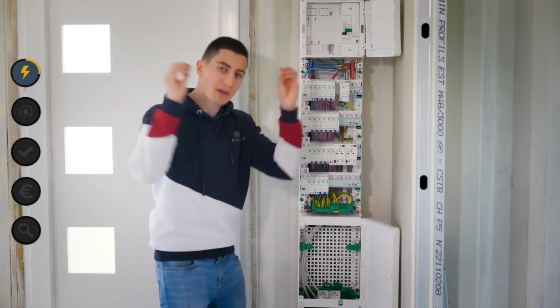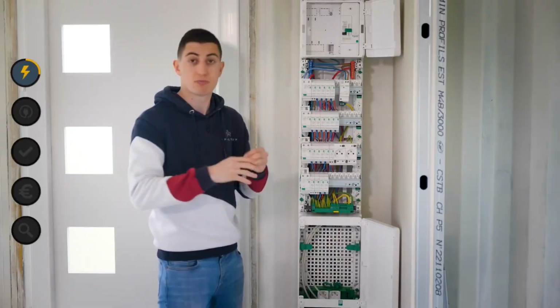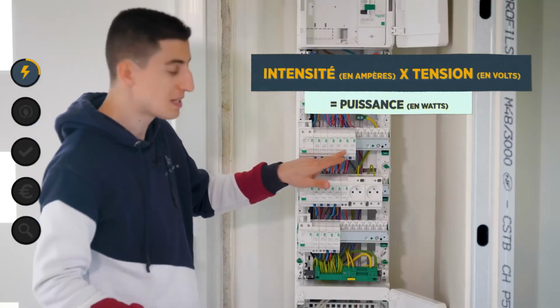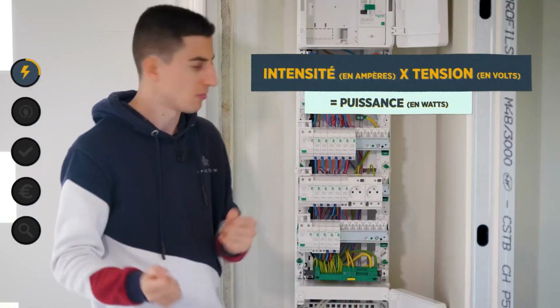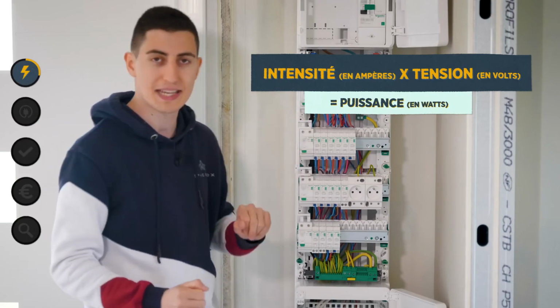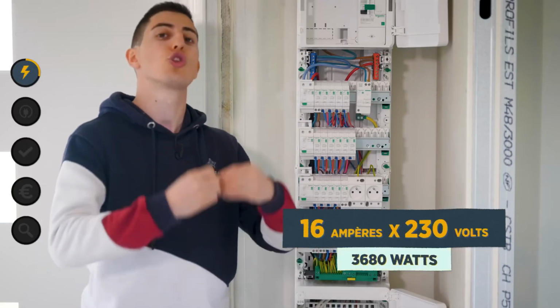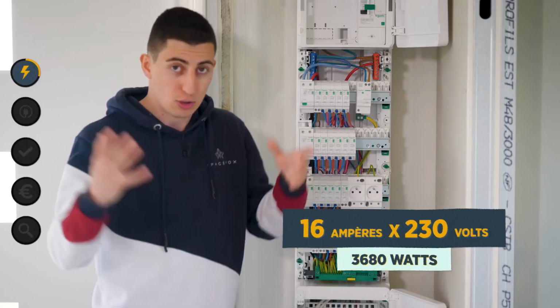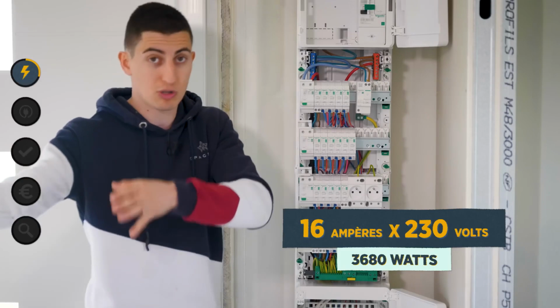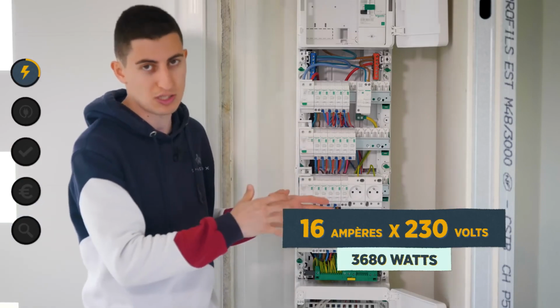If you want to calculate more precisely what power you need, it's simple: just multiply the amperes by the volts. For example, with a 16 ampere circuit breaker on 230 volts, that gives us 16 times 230, which is 3,680 watts. So I could put devices with a power of up to 3,680 watts on this circuit breaker.